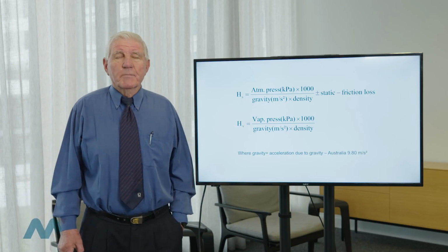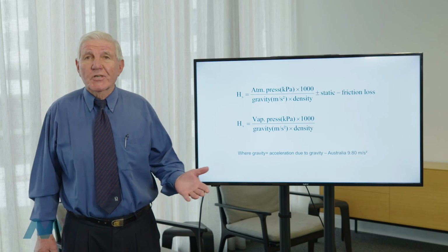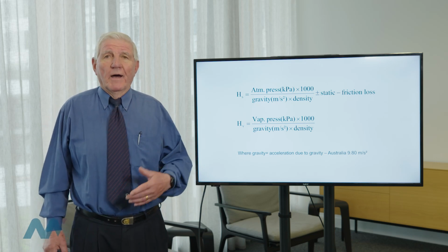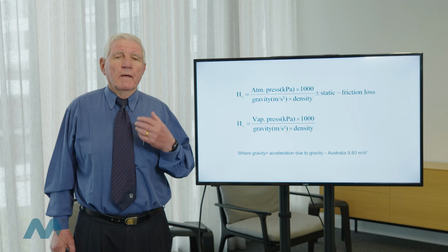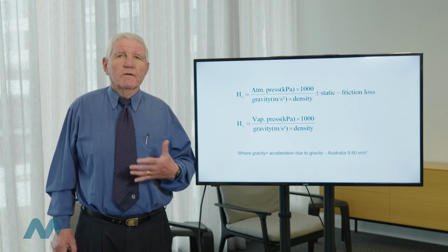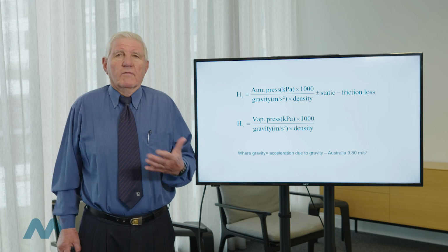If in fact you find on site that the friction losses in the pipework are higher than were calculated, obviously you've got a problem. And this happens a lot. It also happens on the discharge side, doesn't it? People overestimate the head on the discharge side. But those problems you need to find a fix for on the suction side.